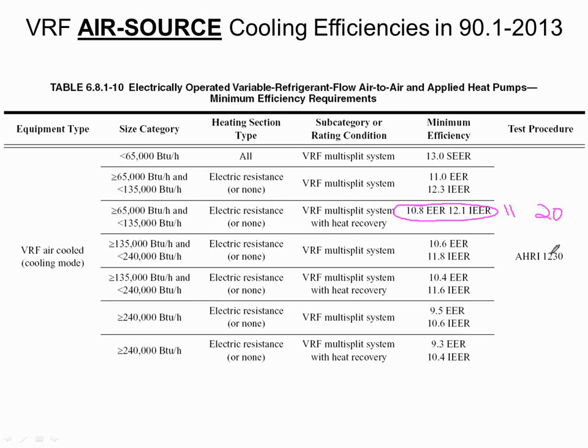You're going to find that very true on all these VRF systems. They're really, really efficient at part load. And the good news is most buildings are at part load a good chunk of the year. So VRF systems do get to be pretty efficient in that regard. A couple other things to note. You'll note that there are ratings for both multi-split systems. So that's basically just your regular heat pump. And there are separate ratings for heat recovery.